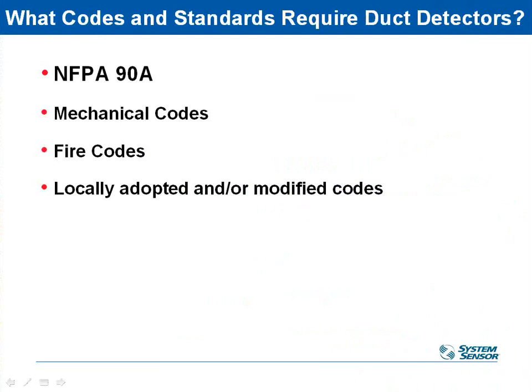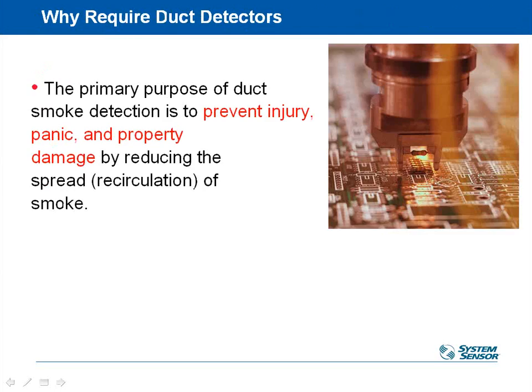All right, so what are the codes that are involved here? There are two primary codes that come up quite a bit. One is National Fire Protection Association Standard 90A. The other one is the International Mechanical Code, either 2006 or 2009, depending on what your community is following. There are also many local fire and mechanical codes that come into play, but we're going to concentrate on NFPA and IMC. NFPA, National Fire Protection Association, IMC, International Mechanical Code. Those are the two that are going to be required most often, and sometimes both, as you'll see.